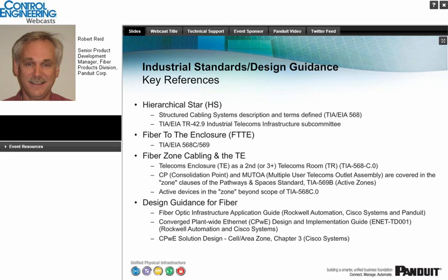So the terms, the telecom enclosure, there's also terms like consolidation point. That would be like a passive zone approach where I just have the large cable broken down into multiple smaller cables. MUTO or MUTOA, multiple user telecommunications outlet. That's another term that is in the 569 standard, and that is another term for a kind of a consolidation point where I have multiple user outlets from one big cable being broken down into multiple cables in one space. The active devices in the zone are beyond 568C.0, and as I mentioned, they're in 569.